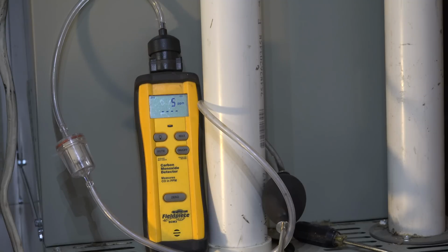So what should it be? I'd rather it was about 10, 11, or 12 like this one had, but oftentimes they're around 30. I'm antsy if it's over 100, and I've got to look pretty close then. But there is going to be carbon monoxide in your vent. It's never going to be zero. So that's testing carbon monoxide both in the ductwork and in the vent pipe.